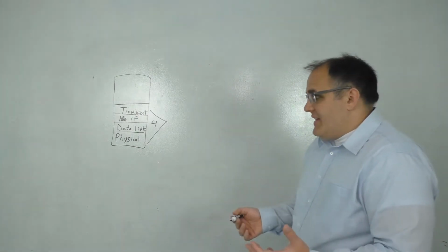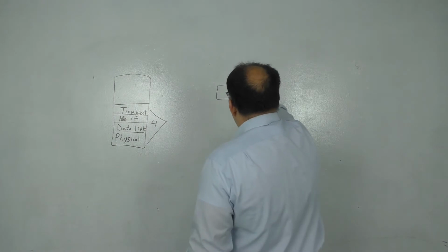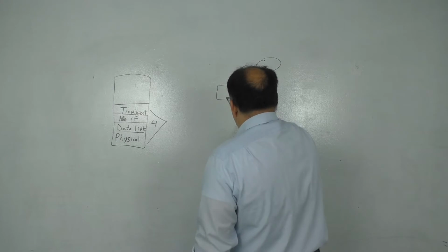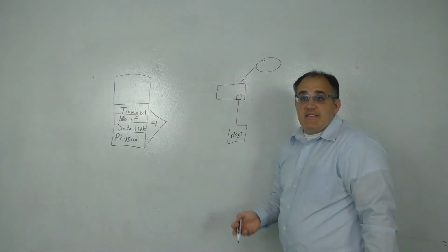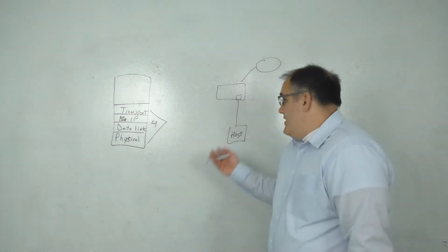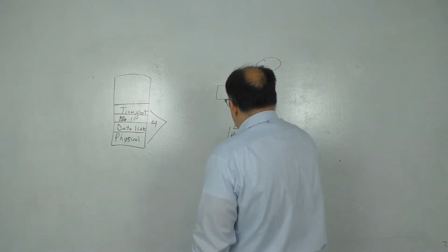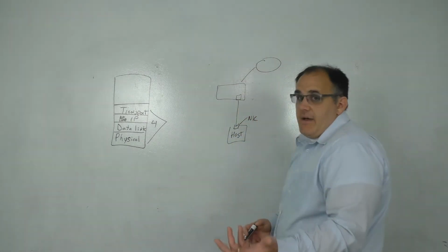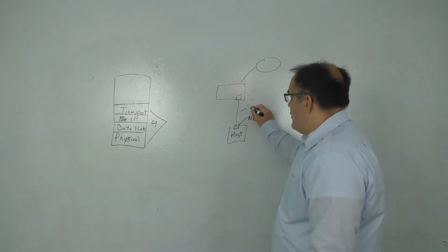All right, so what is the physical layer? Well, first off, let's talk about a network, right? So your basic network consists of really 4 things. So you have a host, and a host is a supervisory device with an IP connection, an IP field controller. That's what a host is, okay? And this host has a network interface card, or a NIC, and that NIC is a port. It has a port coming out of it, okay? And that port has a link. So this is called a link.